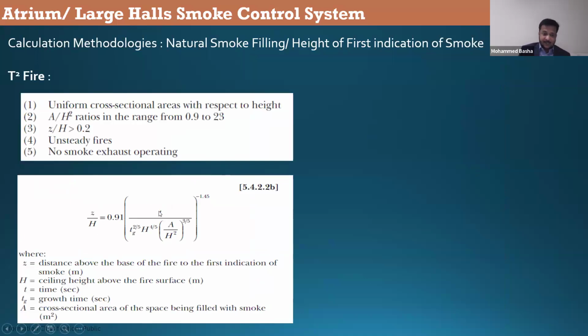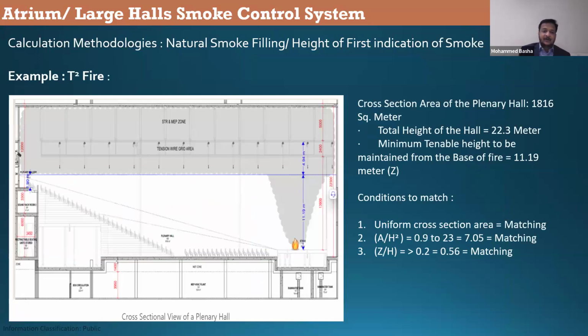So again, this is the formula to determine the time required. Now I have made a sample calculation to make our life easier for the seminar purpose. Let us take an example of an auditorium, because when we see an auditorium, we normally tend to say that a smoke exhaust system is required, right? But do we really need a smoke exhaust system based on this natural smoke filling?